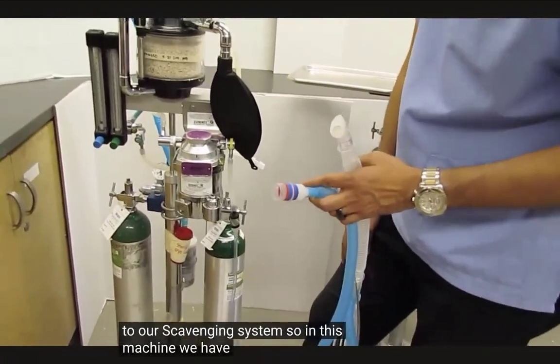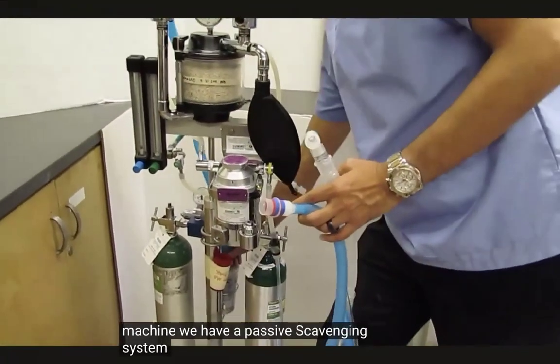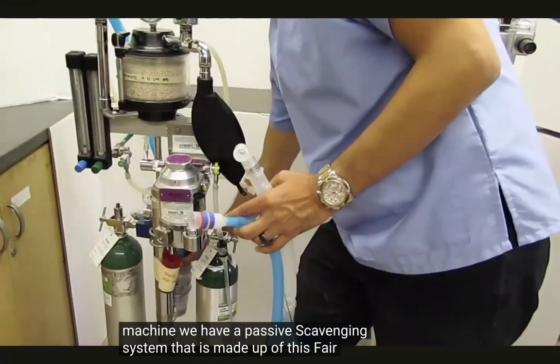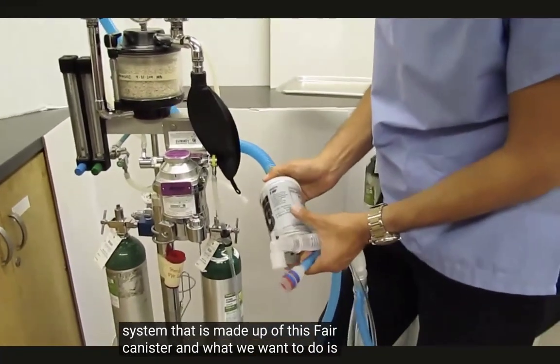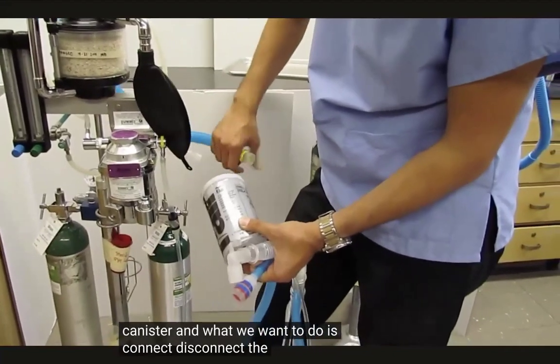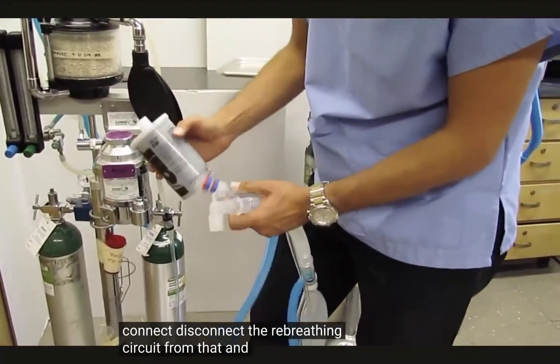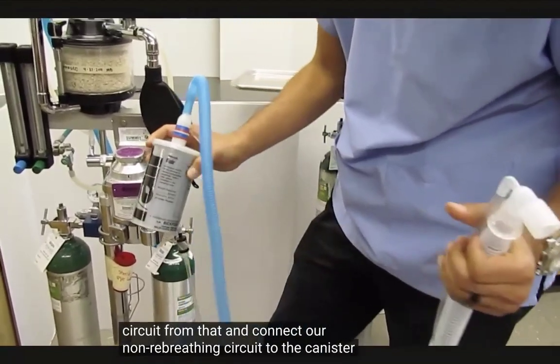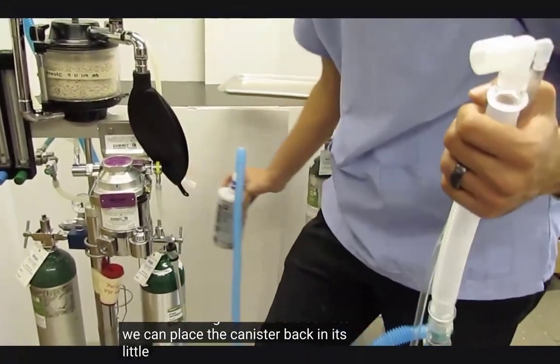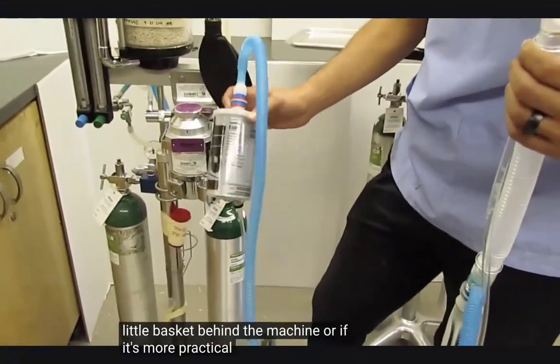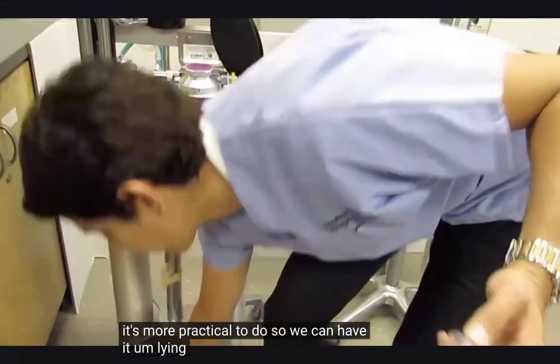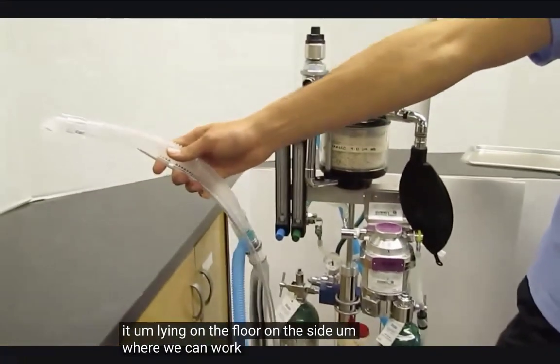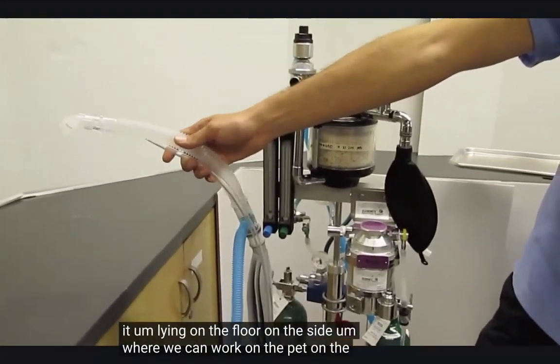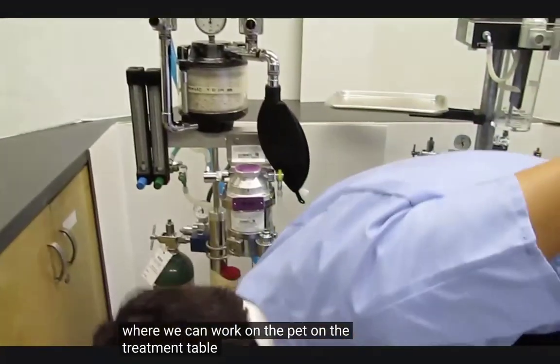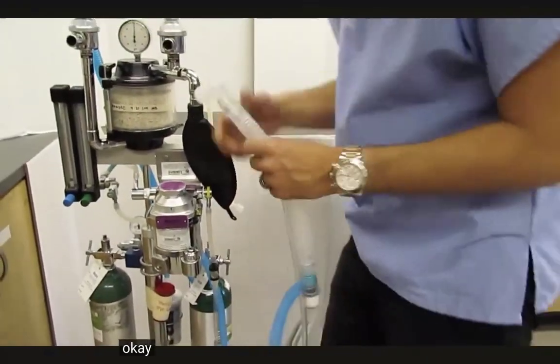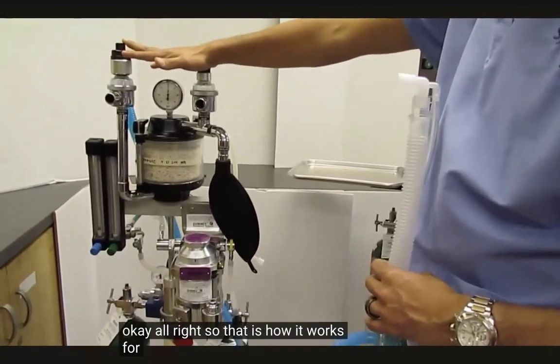So in this machine, we have a passive scavenging system that is made up of this canister. What we want to do is disconnect the rebreathing circuit from that and connect our non-rebreathing circuit to the canister. We can place the canister back in its little basket behind the machine, or if it's more practical to do so, we can have it lying on the floor on the side where we can work on the pet on the treatment table. All right, so that is how it works for this machine.